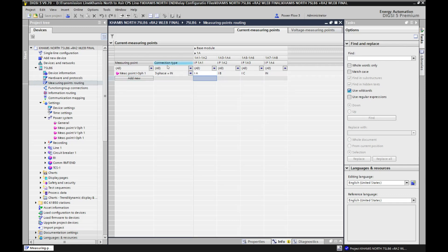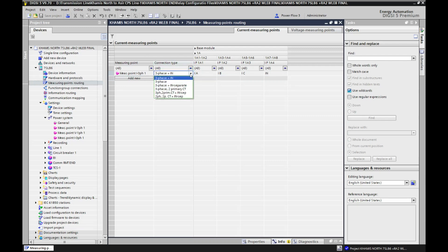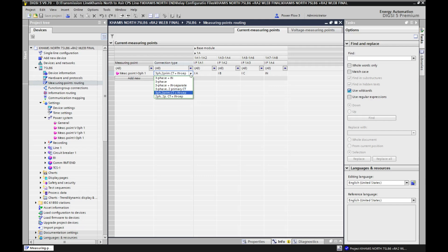Here we have an option to define our CT connection. If we open this dropdown arrow, we have: three phase plus In (neutral), simple three phase, three phase plus In separate (meaning a separate CT is available for neutral), three phase plus two primary CT, and three phase plus two primary CT plus In separate.